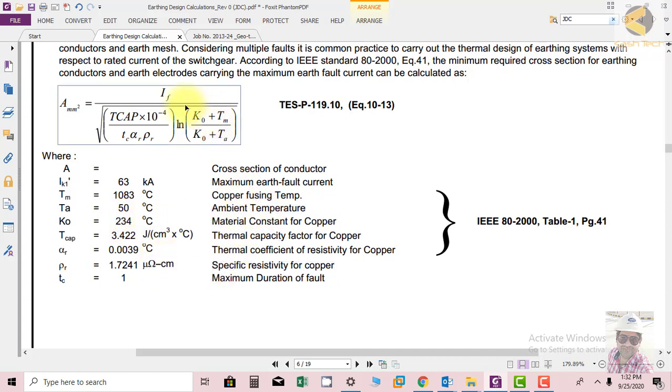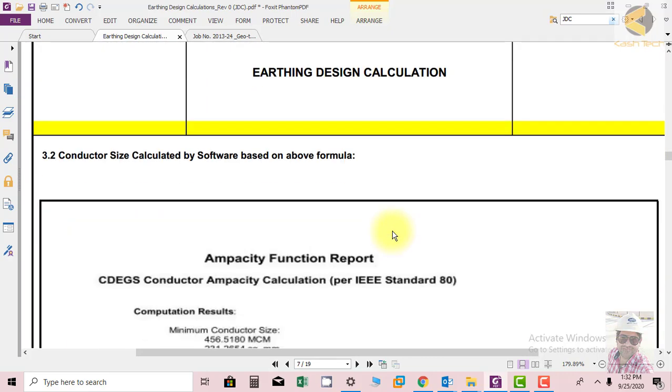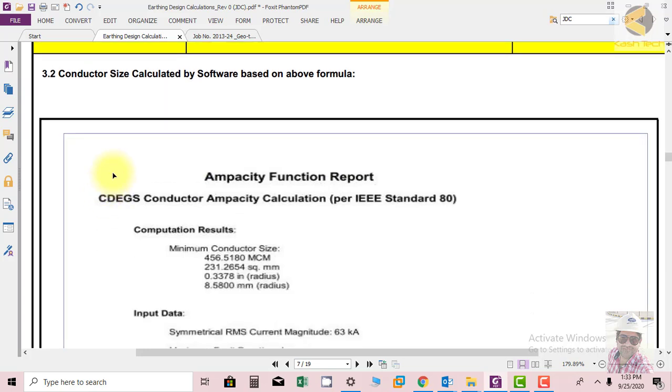You have to put this equation in the calculation also. All these parameter values are with us. The ambient value is also coming from the standard by the utility. We have put all these values and then we can calculate the cross section area. This table is also taken from IEEE 80 2000 page 41. This formula is very famous.